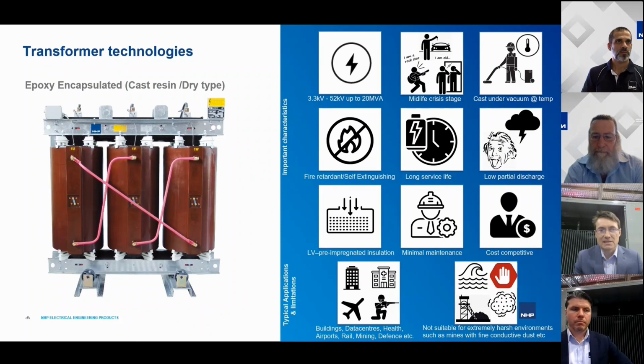For outdoor environments, cast resin transformers have been used a lot these days as well, if the environment is reasonably clean, so there's no dust, especially conductive dust. They're even suitable for installations close to the sea, depending on the type of testing performed on the transformer for environmental categories, which we'll talk about in our next webinar. Where cast resin is not really good is dust environments, conductive dust, mining; in those areas you have to be careful. There's no one rule, you just have to look at the environment.